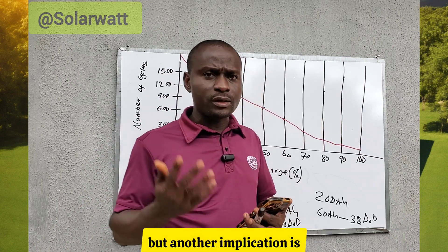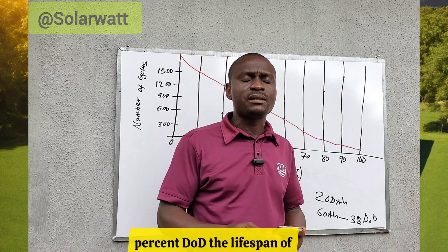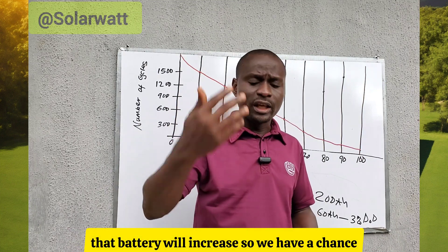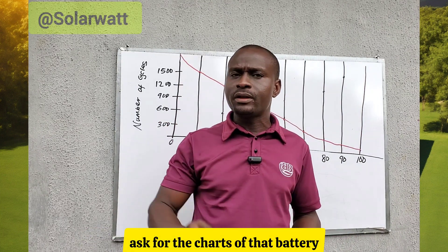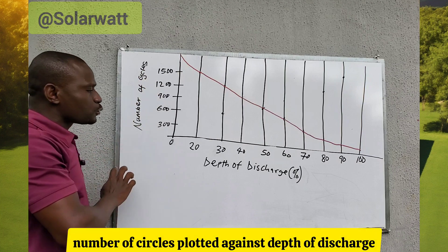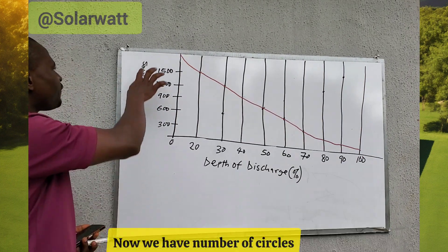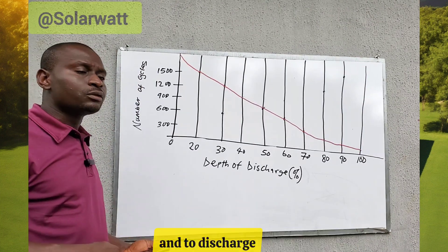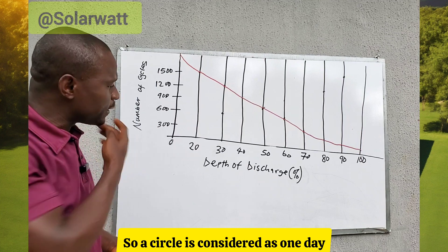Another important implication: when you deeply discharge a battery — using a high DoD of 50%, 60%, 70%, or 80% — the lifespan of that battery will be reduced. If the DoD is low, the lifespan will increase. Whenever you buy a battery, ask for the datasheet. Inside the datasheet you will find a graph of number of cycles plotted against depth of discharge. A cycle is the time it takes for a battery to charge and then discharge — one cycle equals one day.